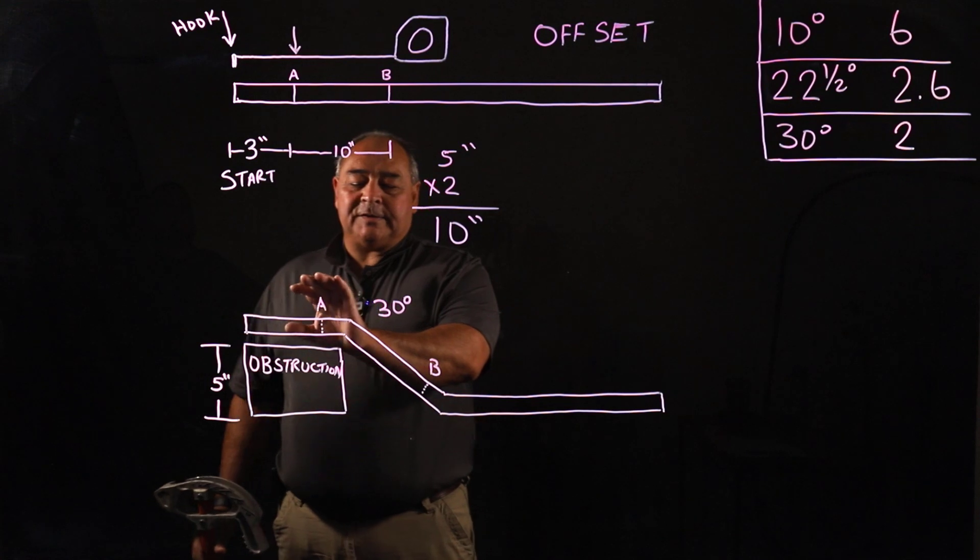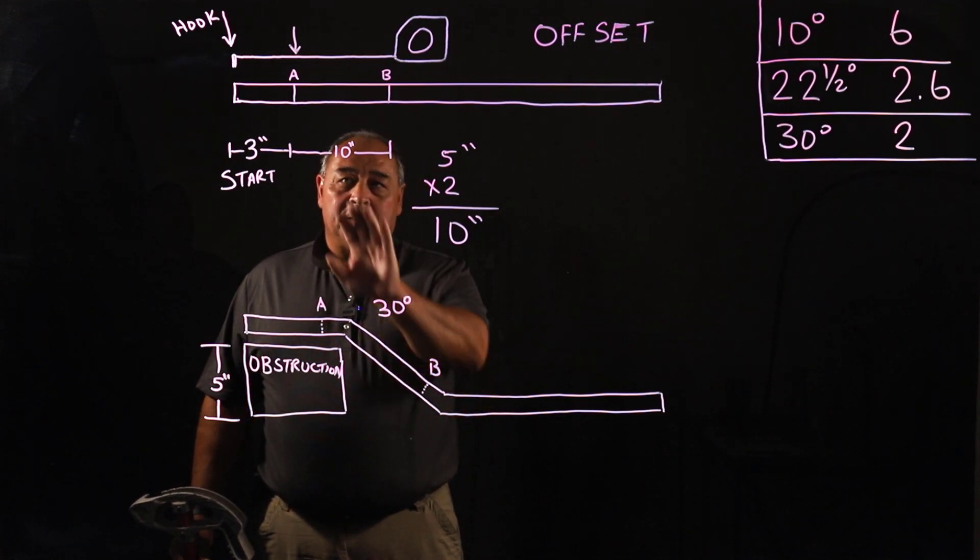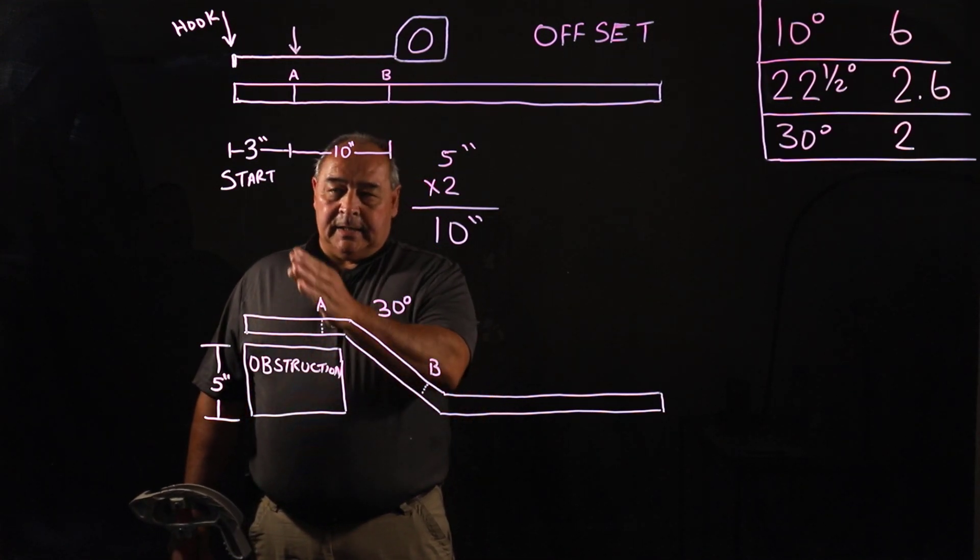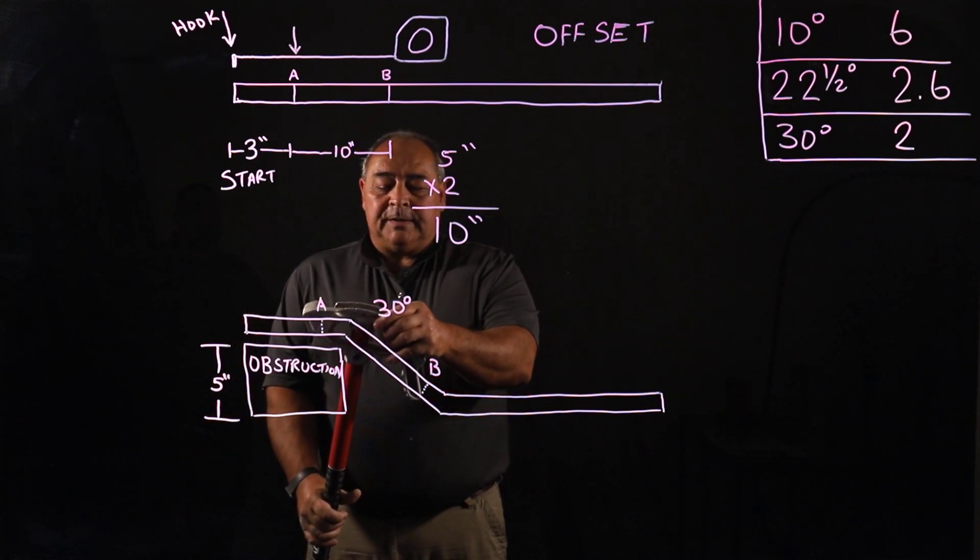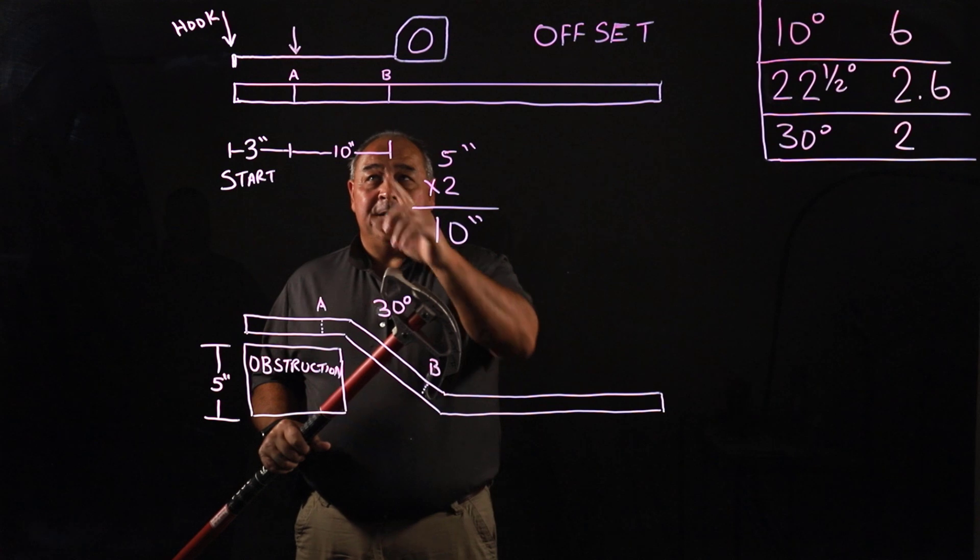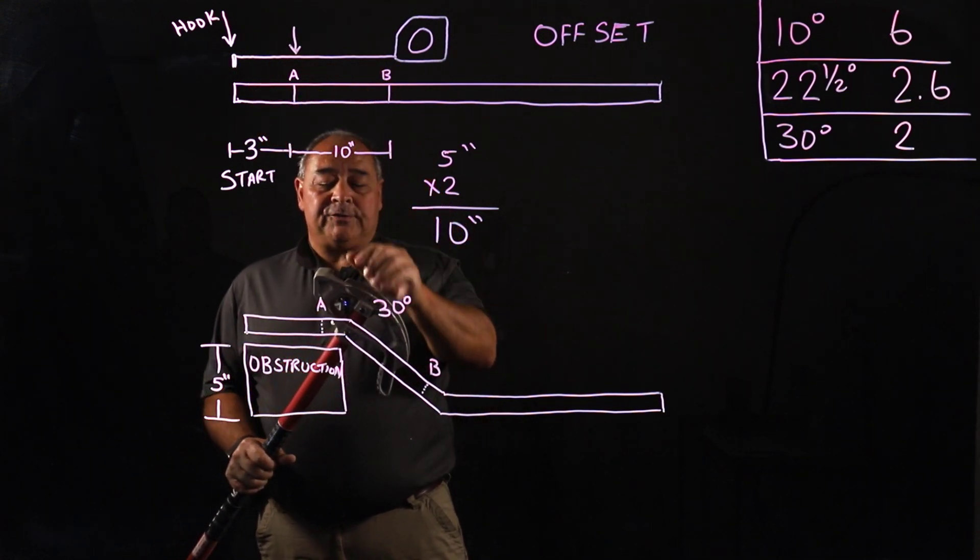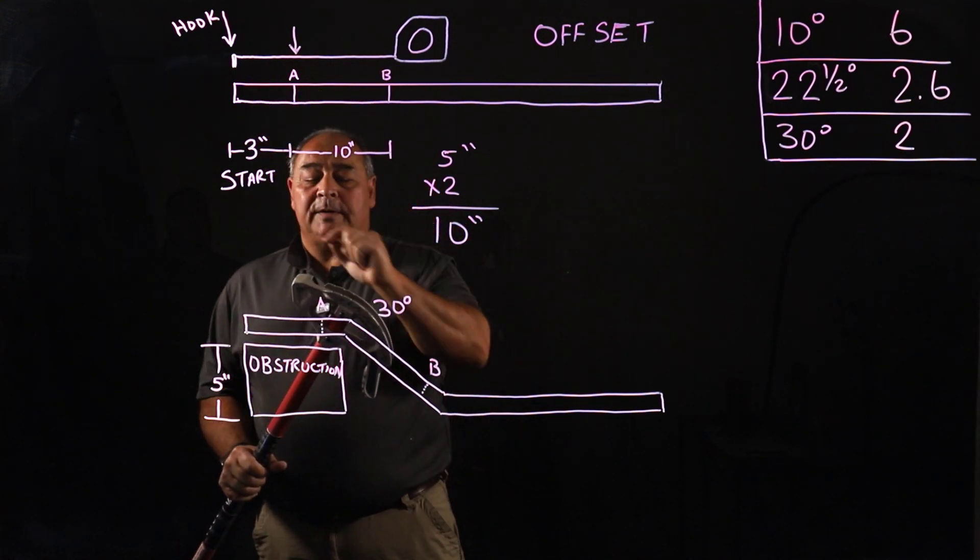And to bend this, once we established our A and B marks that are 10 inches apart, again I suggest it starting at three, we'd bend the first bend with our hook, the same orientation as the way we measured. The hook of the bender, the hook of the tape measure. You put this on the arrow on the bender.